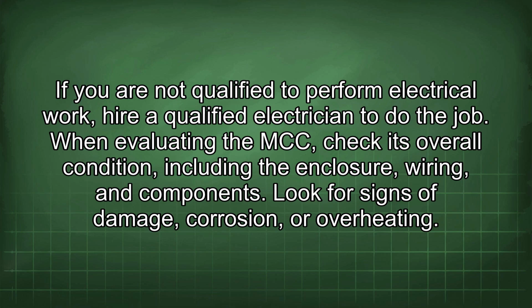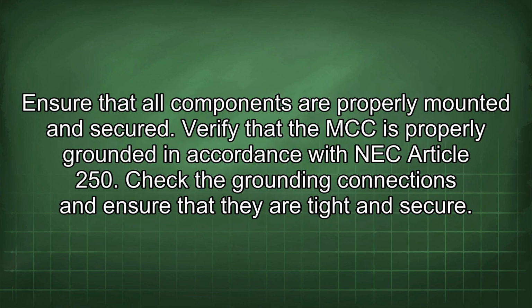When evaluating the MCC, check its overall condition, including the enclosure, wiring, and components. Look for signs of damage, corrosion, or overheating. Ensure that all components are properly mounted and secured. Verify that the MCC is properly grounded in accordance with NEC Article 250. Check the grounding connections and ensure that they are tight and secure.